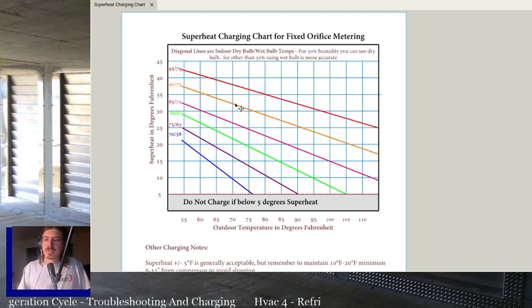It was almost 100 degrees outside. The house got up to 90 degrees, but the outdoor temp's starting to drop. So it's actually 90 degrees inside, 80 degrees outside. So you go 90 degrees, line that up with 80 degrees right here. So that's the outdoor temp. This is your indoor temp. You follow it over, you're going to have like 28 degrees of superheat.